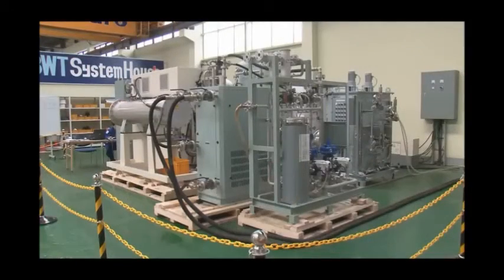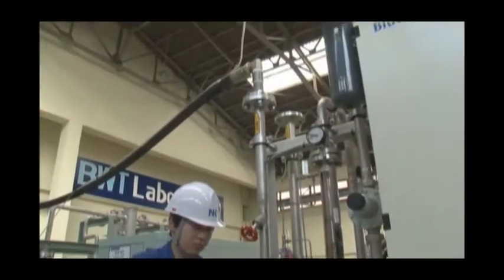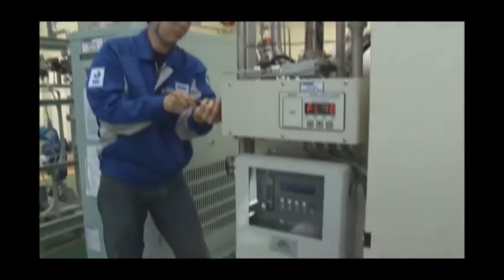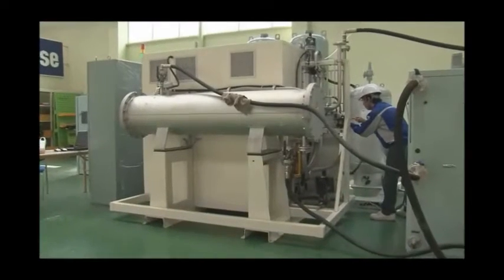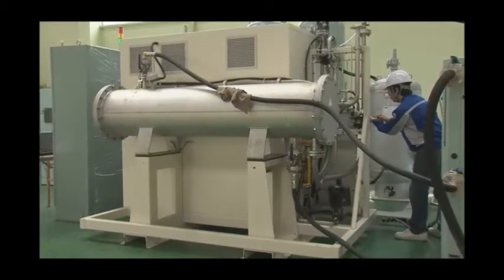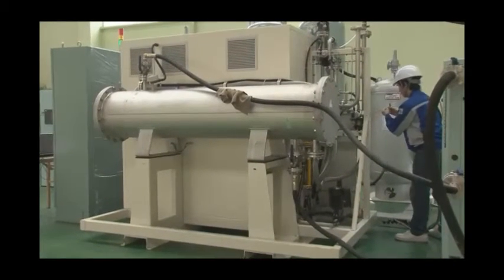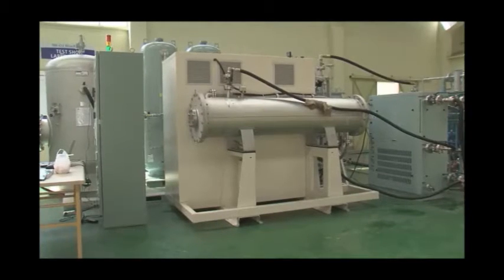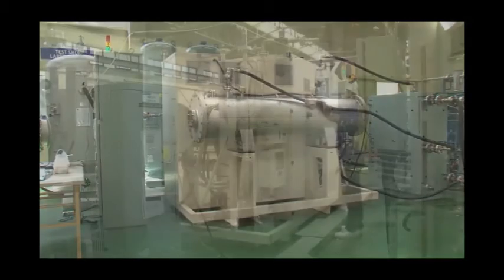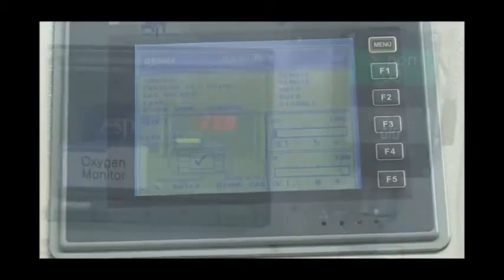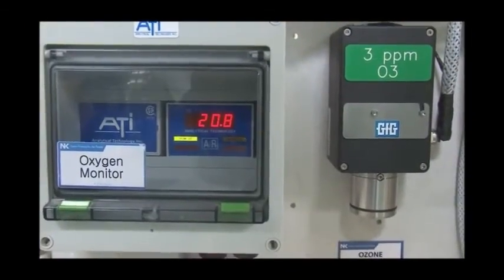Oxygen pressure directed to the ozone generator is reduced to 1.1 bar by pressure regulator at inlet of ozone generator. The oxygen crosses between electrodes in this generating chamber and micro discharge is taking place between electrodes with high voltage electric source from generator panel. And this results in dissociation of oxygen atom which recombines with the remaining oxygen molecules to form ozone.